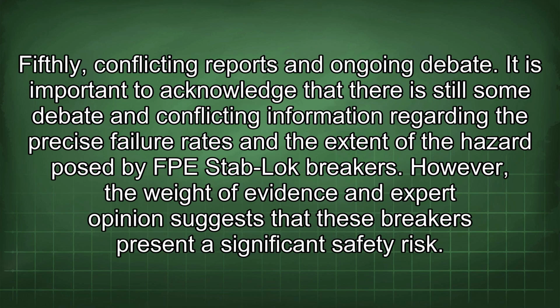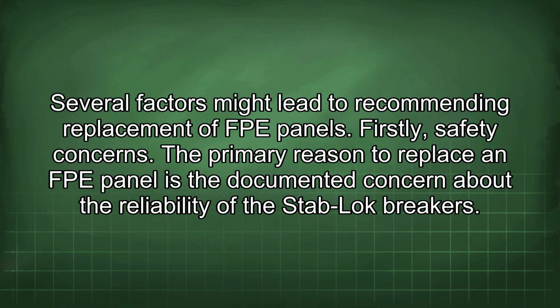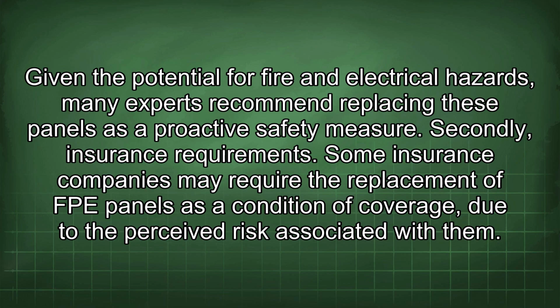Fifthly, conflicting reports and ongoing debate. It is important to acknowledge that there is still some debate and conflicting information regarding the precise failure rates and the extent of the hazard posed by FPE Stab-Lok breakers. However, the weight of evidence and expert opinion suggests that these breakers present a significant safety risk. Several factors might lead to recommending replacement of FPE panels. Firstly, safety concerns. The primary reason to replace an FPE panel is the documented concern about the reliability of the Stab-Lok breakers. Given the potential for fire and electrical hazards, many experts recommend replacing these panels as a proactive safety measure. Secondly, insurance requirements. Some insurance companies may require the replacement of FPE panels as a condition of coverage due to the perceived risk associated with them.